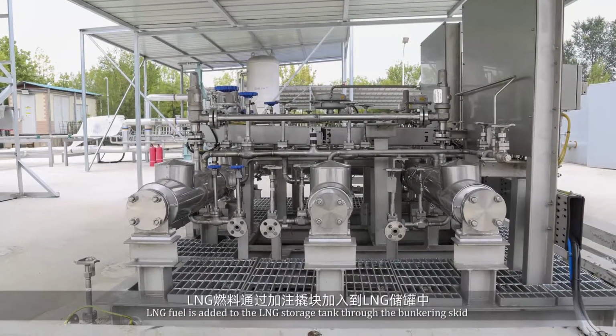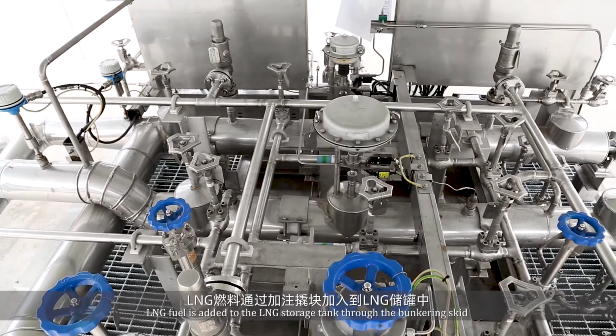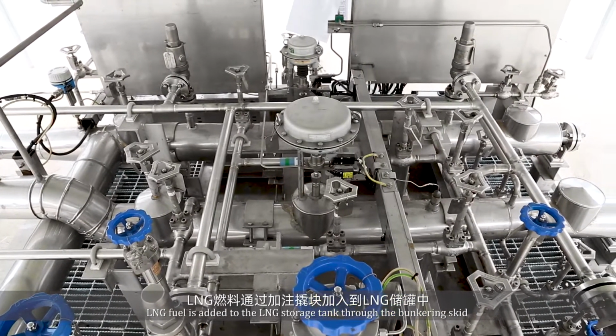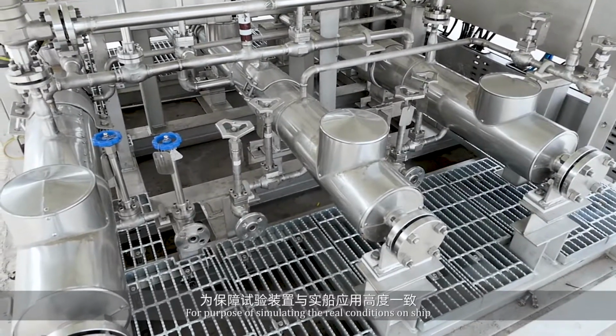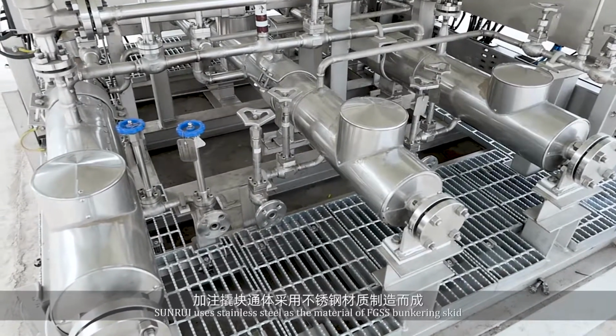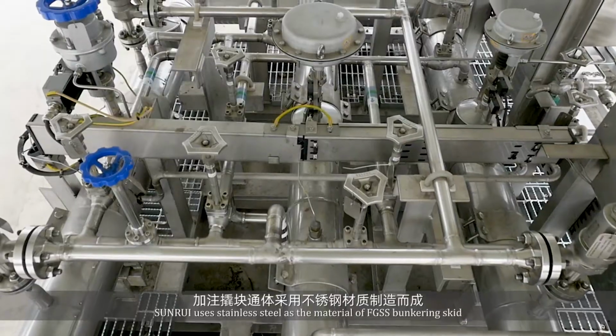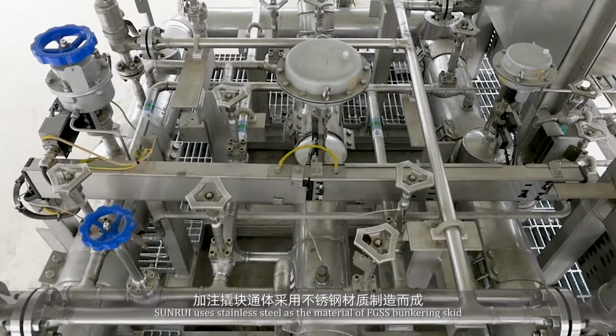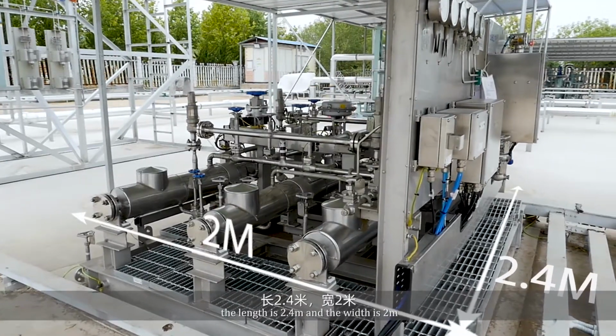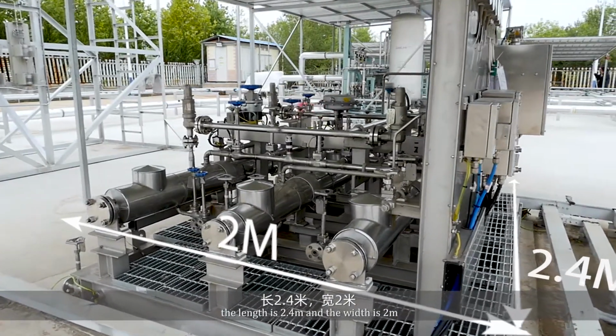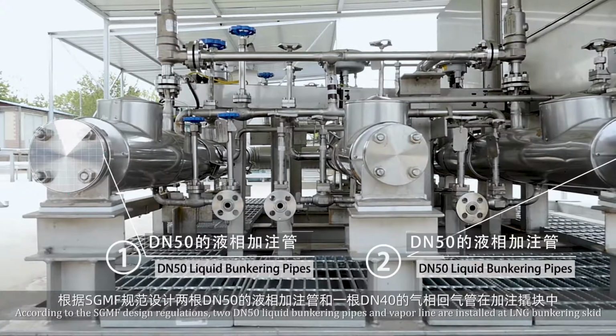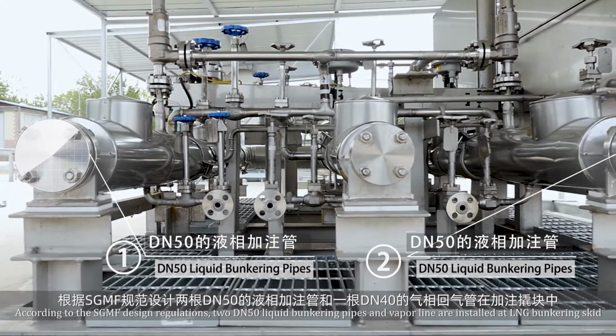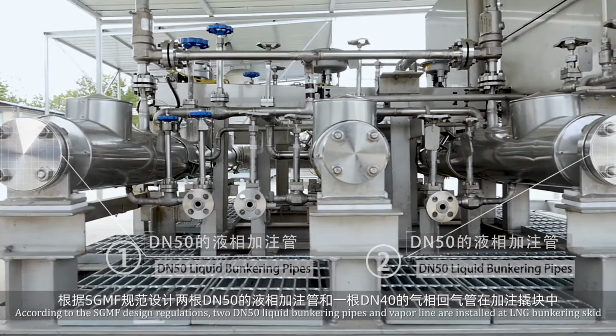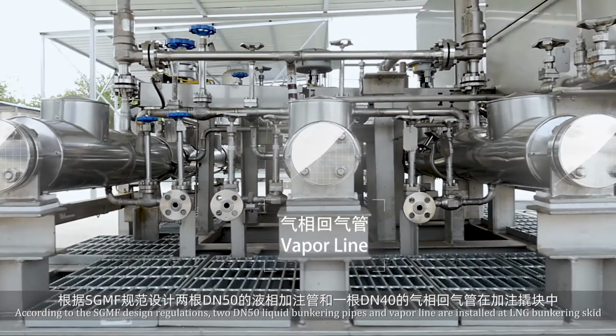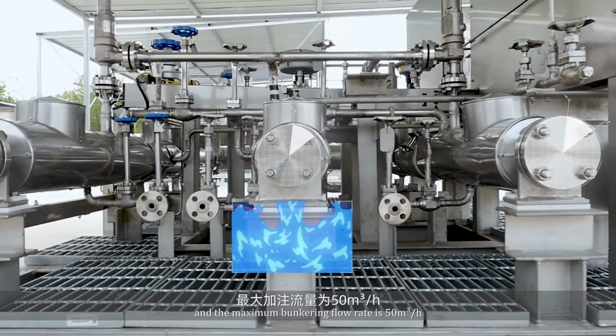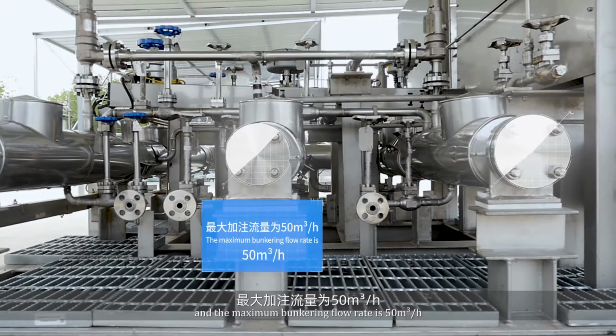LNG fuel is added to the LNG storage tank through the bunkering skid. For the purpose of simulating the real conditions on ship, SunRui uses stainless steel as the material of the FGSS bunkering skid. The length is 2.4 meters and the width is 2 meters. According to the SGMF design regulations, 2 DN50 liquid bunkering pipes and a vapor line are installed, and the maximum bunkering flow rate is 50 cubic meters per hour.